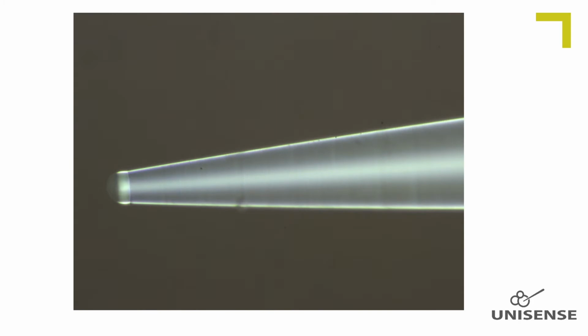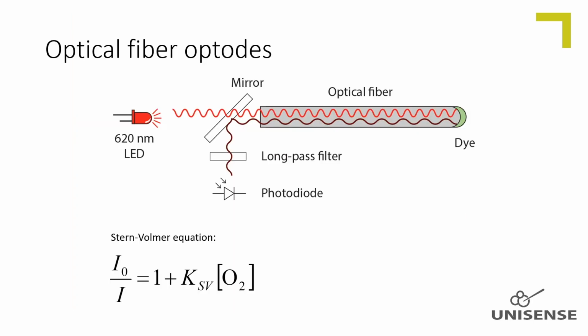This is a photo of the glass fiber equipped with a dye-containing polystyrene matrix. The fiber is tapered using an etching technique. The fiber is connected to an optode meter, which illuminates the dye by an LED. The light excites the dye, which emits light back with a longer wavelength. With the use of mirrors, filters and photodiodes, the intensity of the fluorescence is detected, which is inversely correlated with the oxygen partial pressure at the fiber tip.